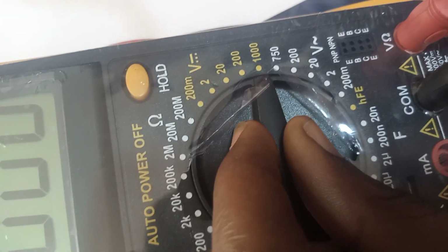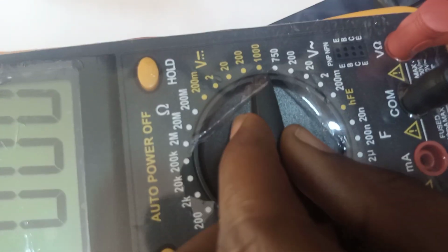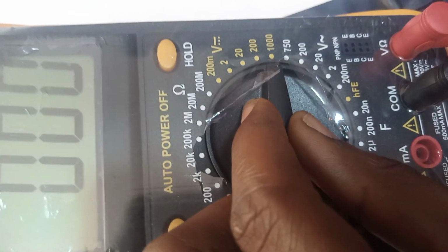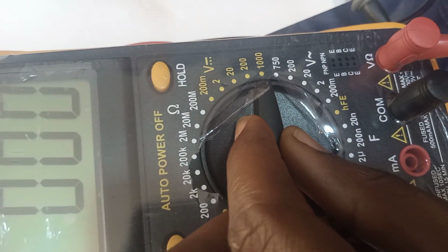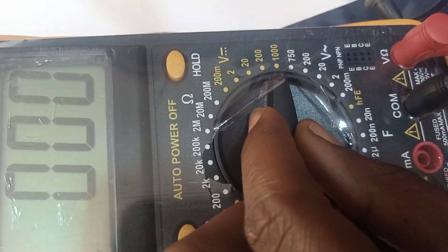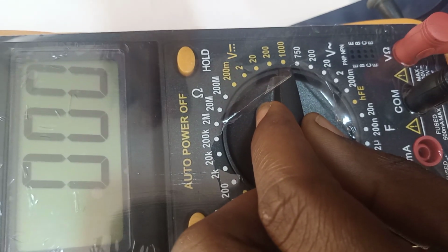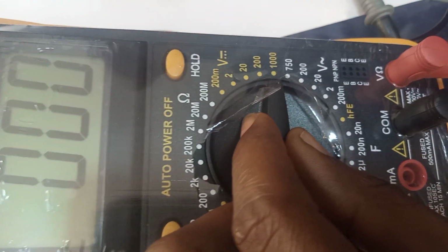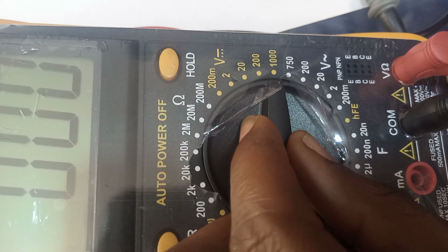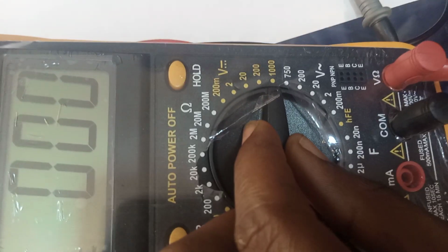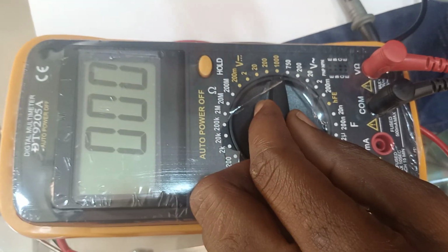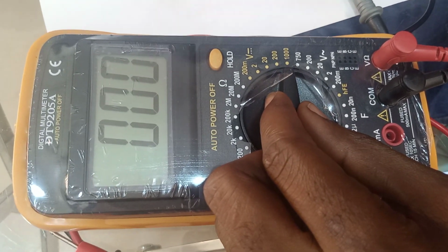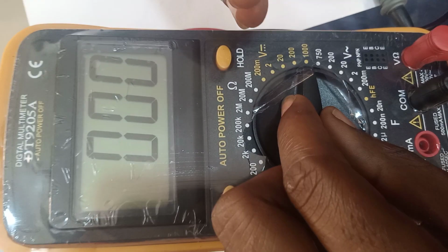And if the voltage is above 200 volt DC, what you should actually do is put it on max, the 1000 DC voltage. Like in the case of fixing a laptop charger or a device, after the capacitor you are trying to check the voltage across it, you have to put it on 1000 DC volts, because across that point the capacitor must have boosted your input voltage, and it will rise maybe to around 300 volts or 200, depending on the voltage standard in your country. So this is how that works.